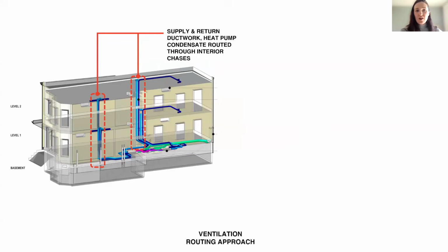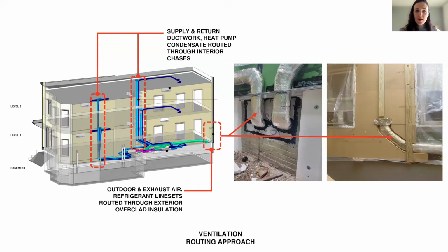We have a ventilation routing approach that sees us installing supply and return ductwork from ERVs in the basement to the units themselves, as well as heat pump condensate, which is routed throughout in interior chases, back draining to the basements. And then for the outdoor and exhaust air from the ERVs, as well as the refrigerant lines, we're actually routing them through the exterior overclad insulation. So they're basically poking out through the water table, coming up through a datum line between the water table and above, and then they're just getting away from each other so that we can get our clearances and that we can locate them far enough away from operable windows. So each unit has a slightly different configuration for how that works.